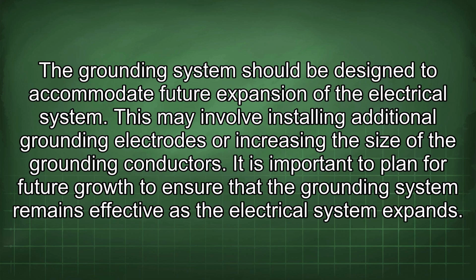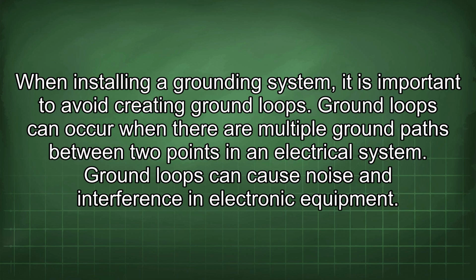The grounding system should be designed to accommodate future expansion of the electrical system. This may involve installing additional grounding electrodes or increasing the size of the grounding conductors. It is important to plan for future growth to ensure that the grounding system remains effective as the electrical system expands. When installing a grounding system, it is important to avoid creating ground loops.